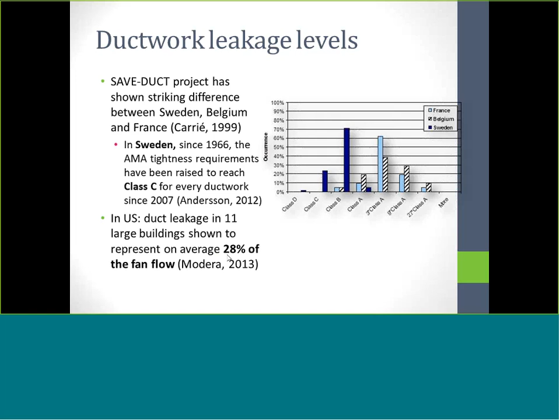Going from Class A to Class C may reduce fan energy use by 50%. So there is some work to be done. This has been confirmed by a US study on 11 large buildings, which showed that ductwork leakages represent 28% of the fan flow.